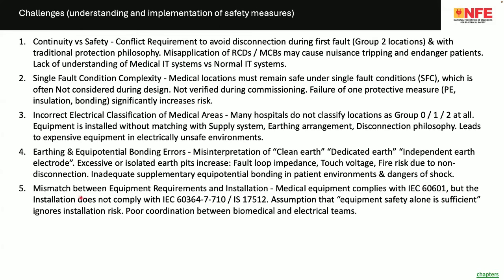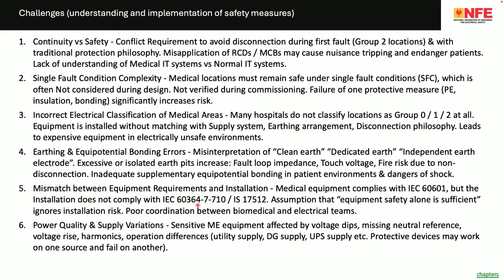Now, the installation does not comply with the respective installation standard. What this means is you have equipment which is very good. Now you are putting it in a room, in a location where there is electrical supply. If the supply is not in compliance with the standard, of course, the chance of an accident is very high.